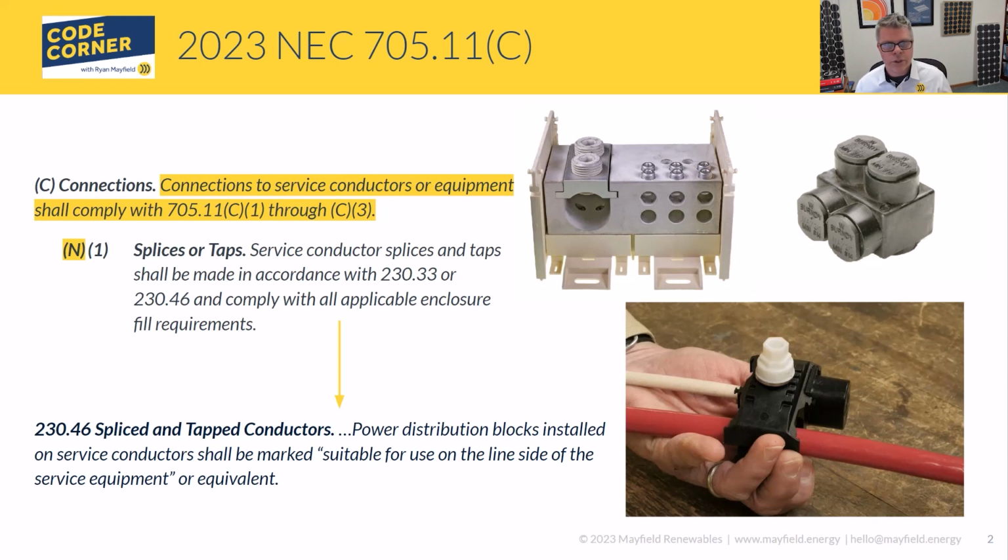One of the things you'll notice again with these, if you're doing supply side connections, you are likely going to have to call out the utility to pull the transformer or pull the meter so that you can make those connections safe, so you can actually get to them, pull the conductors out, put your connections in, and reconnect to the service.